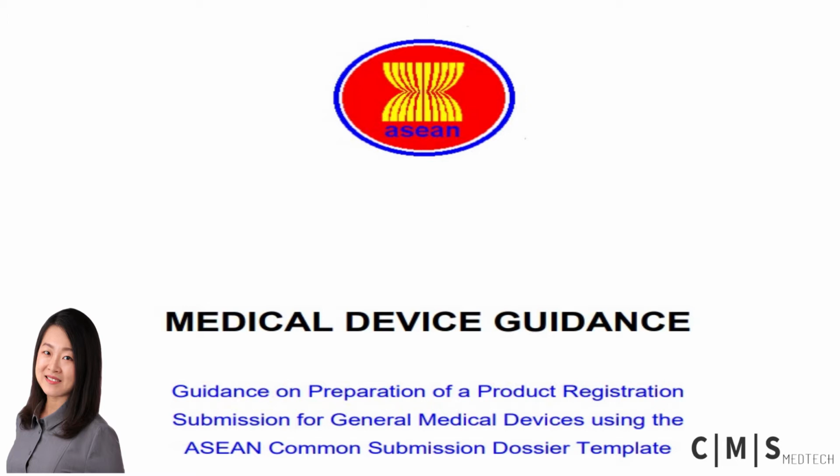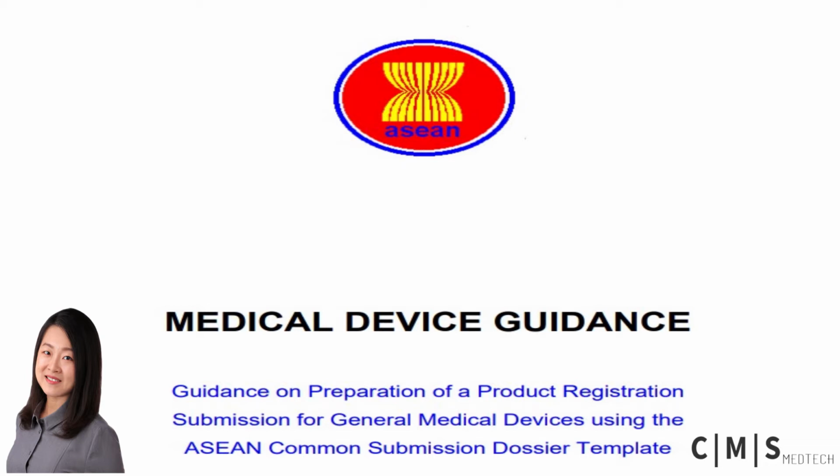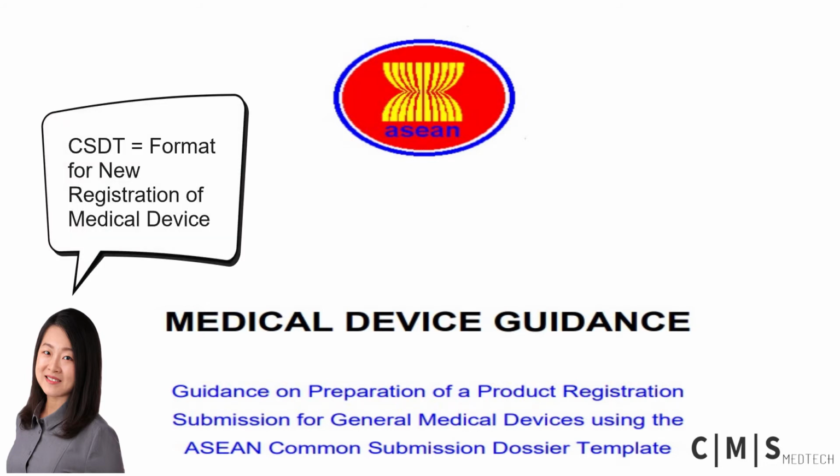For this episode, we are going to go through the specific steps on how to compile a common submission dossier template, also known as the CSDT. But what is the purpose of the CSDT exactly? In short, it is a particular format recognized by the ASEAN authorities for organizing medical device technical documents for the purpose of regulatory submission.